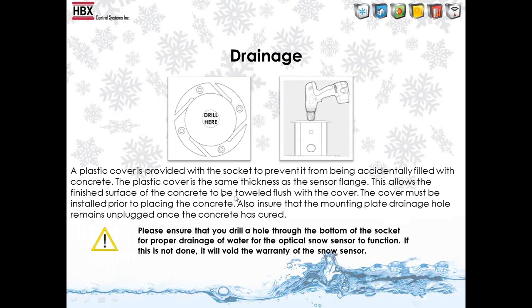The second one was drainage. We had some instances where people would not drain the snow melt socket, and it would fill up with water and then freeze. You know what happens when something filled with water freezes. Basically it will crack and wreck the sensor built into here. It's actually epoxy filled, so it will break this sensor and wreck it. So we tell people to drill in the bottom of it. We actually put a sticker in the bottom of the socket that says "Drill here," so that people will drill it out and make sure they have proper drainage out the bottom of it.